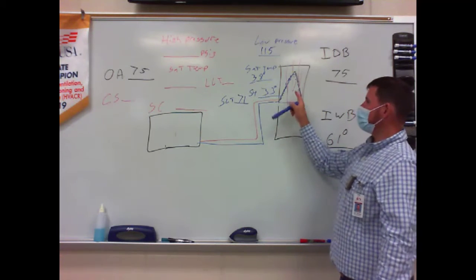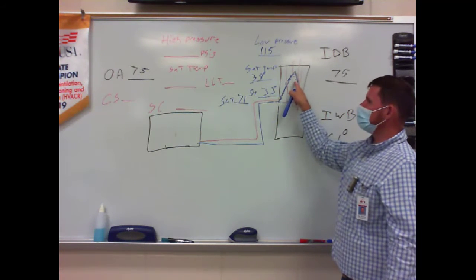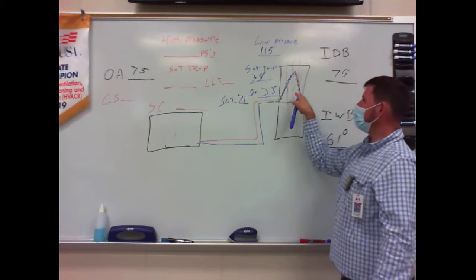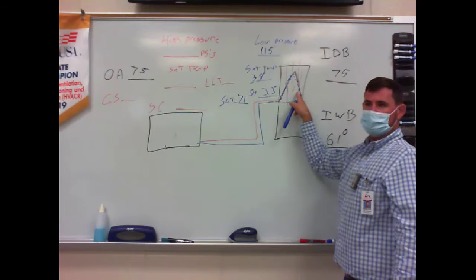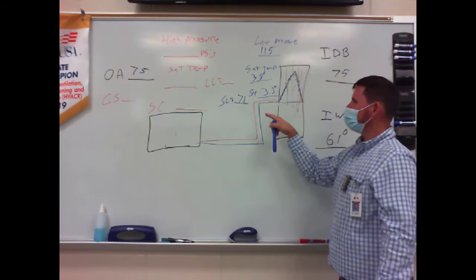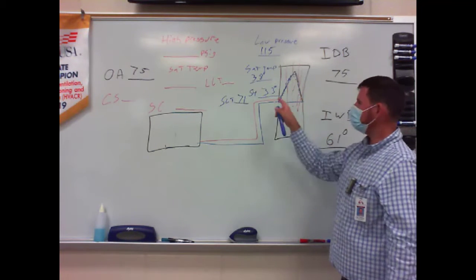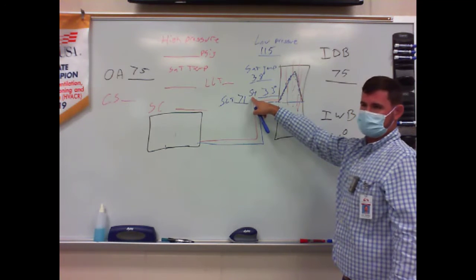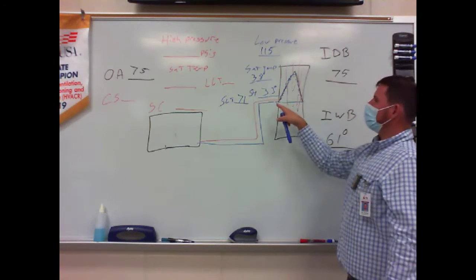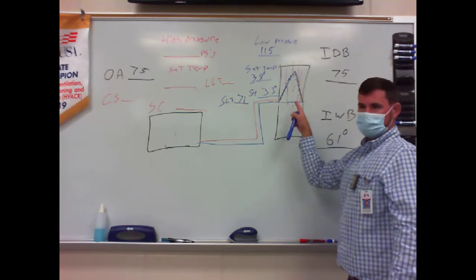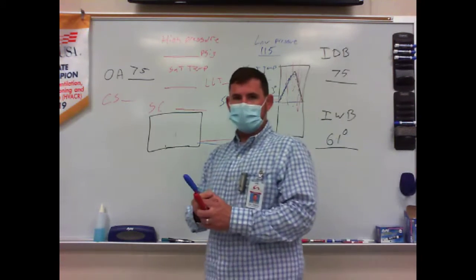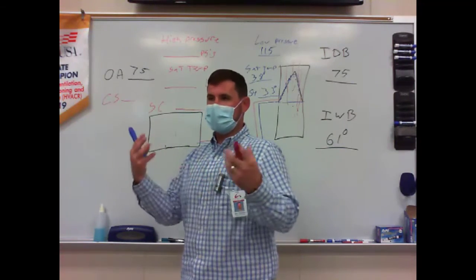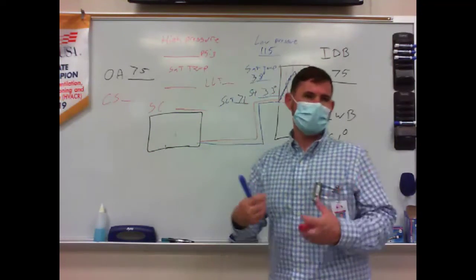I'm starved because I'm boiling all my refrigerant off too soon, and I'm picking up too much heat by the time I leave. There's too much vapor in there. There shouldn't be that much vapor. So the higher the number, the more vapor is in it? Yes, the higher the superheat, the more vapor is in the system. I don't want that much vapor in there. I need to be going from a liquid to a vapor because that's when that big heat transfer takes place, right? All that latent heat, that's when I'm absorbing it.